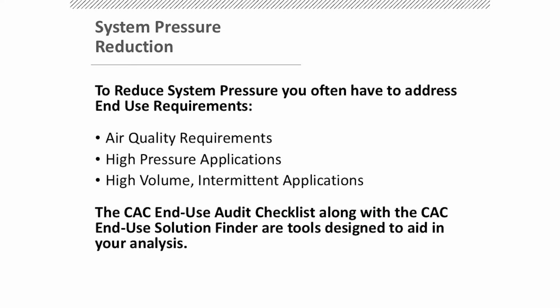So some of the system requirements that you have to address to do this: air quality requirements. You have to have the quality that's necessary for whatever the need or process is, whether that's instrument air or general purpose air. There's a whole ISO procedure that talks about air quality. Really, the key is many times people don't know what quality they need. They spec something because they think it needs to be the best it can be. And the problem is, every time you get better quality, what do you need to do? You need either filter level or you have to go to different dryers.